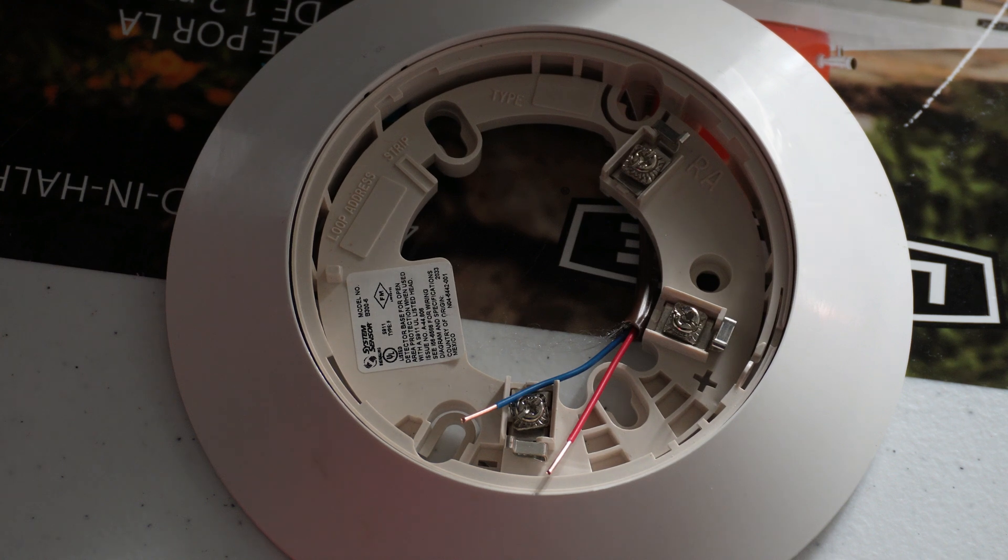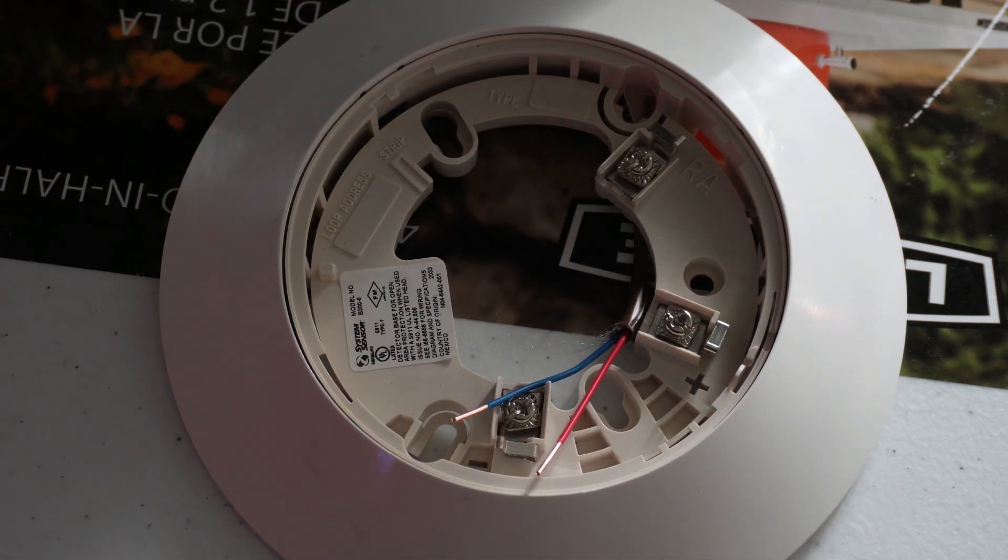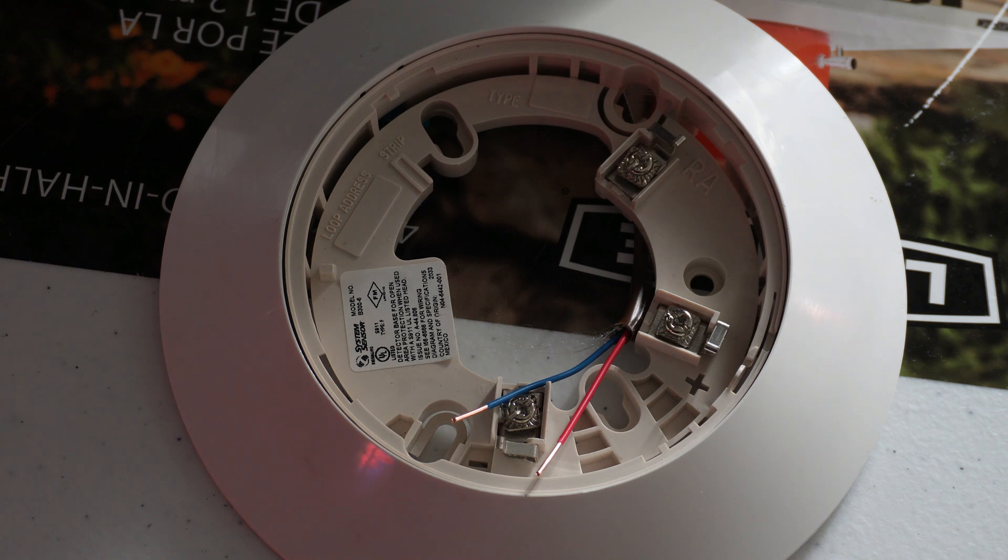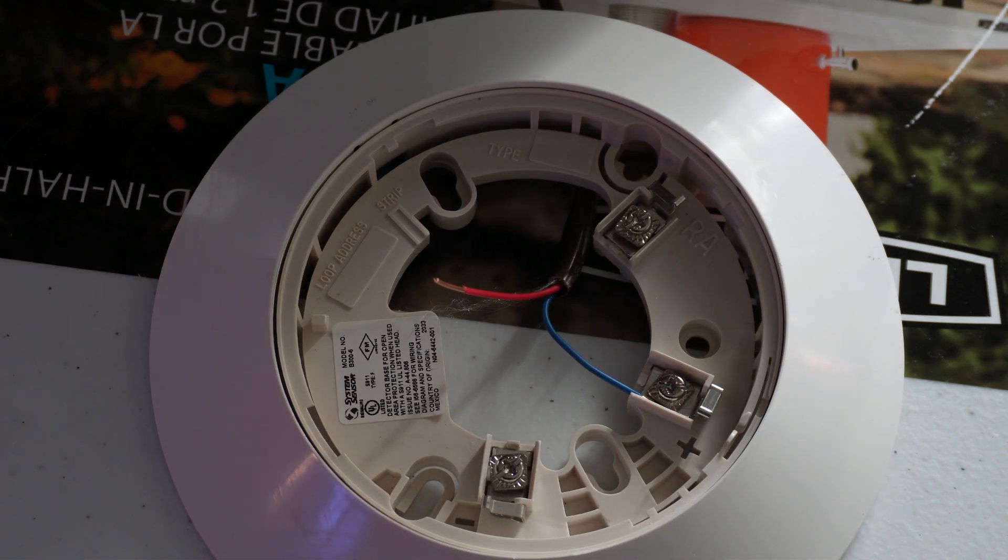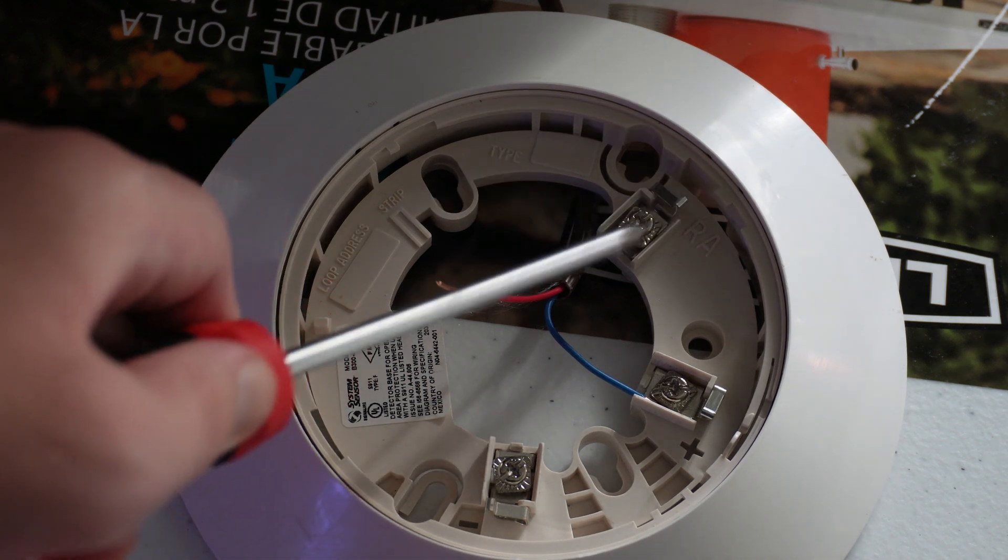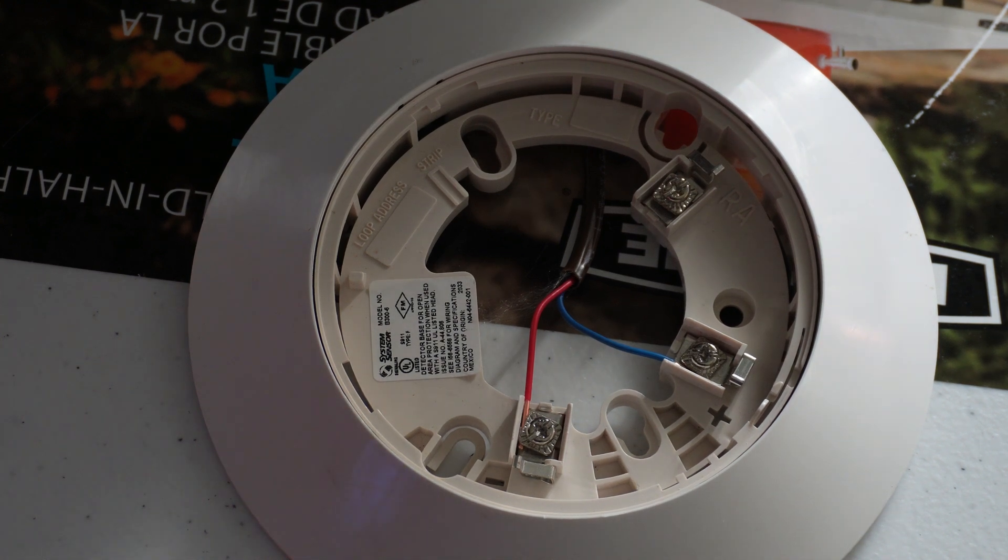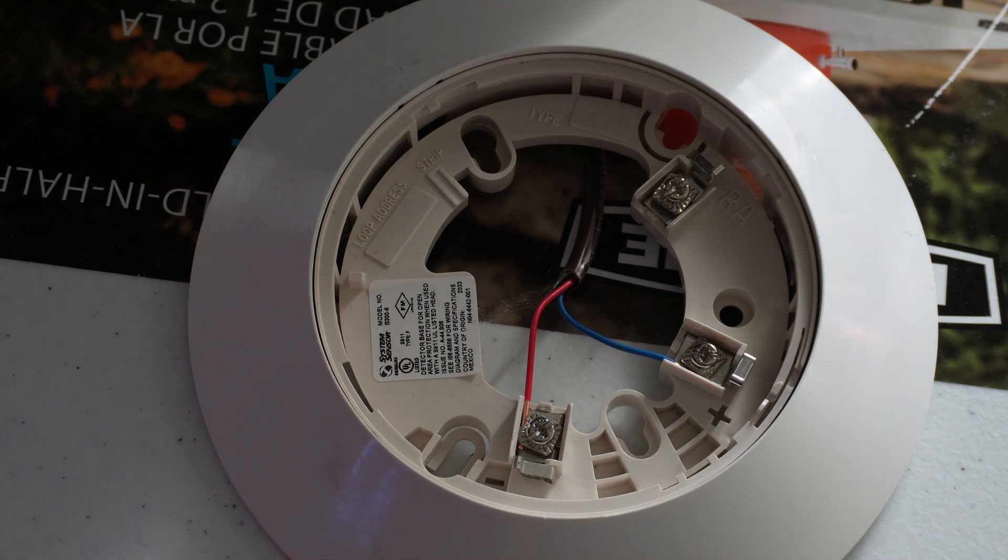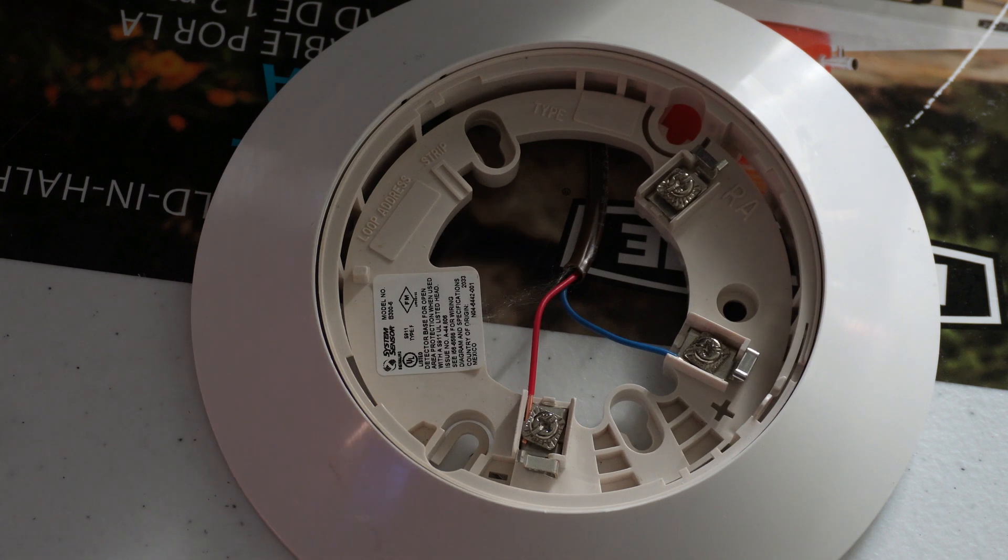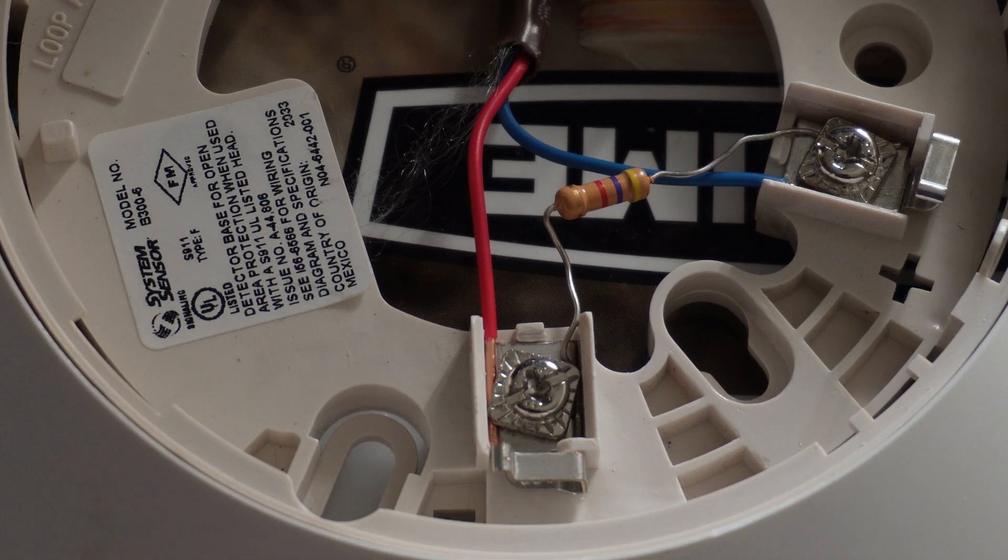Here is the base of the smoke detector. Right next to this terminal, you see positive. That is where the blue wire is going to go since we used blue as B plus on the SLC. Since we used red as negative on the SLC, it's going in this terminal right here. That just doesn't have any marking next to it, that one says RA but that's something unrelated. Now that both of those wires are in there, we need to put the end of line resistor bridging across those two terminals and those two wires.